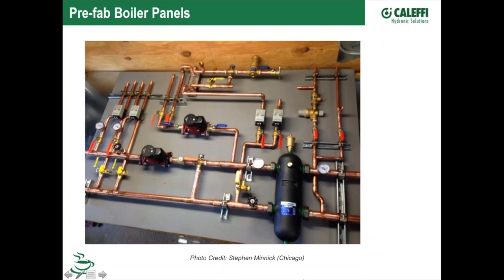Here's a job thanks to Stephen Minnick in the Chicago area. I think probably one of the nicest piping jobs you've ever seen. You can see here he's put together a few of our components. You can see the hydro separator there. You can see the fill valve. Sometimes guys put an additional air removal device on this. So here he's got air removal on the hydro separator. So maybe for the boiler side of this, he's saying, well, that's going to handle my boiler side, make sure I get my air removal quick and efficiently.